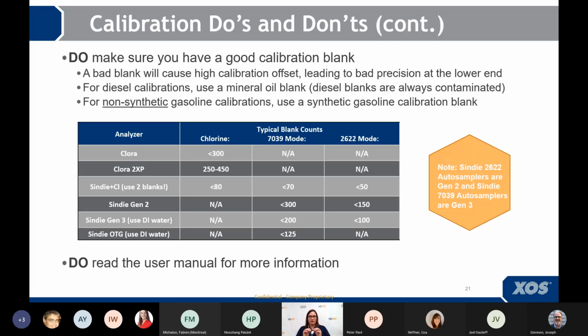It's very, very, very important to have a good calibration blank, okay? A bad blank will cause a high calibration offset, and you'll get very poor precision at the lower end. So it's very important that you have a good blank. You want to consider substitution rather than using a bad blank. For example, if you are using a matrix match calibration, the diesel calibration, we would recommend that you take that diesel blank and toss it, because most diesel blanks aren't blank. They're always contaminated. We'd recommend you substitute mineral oil for that.